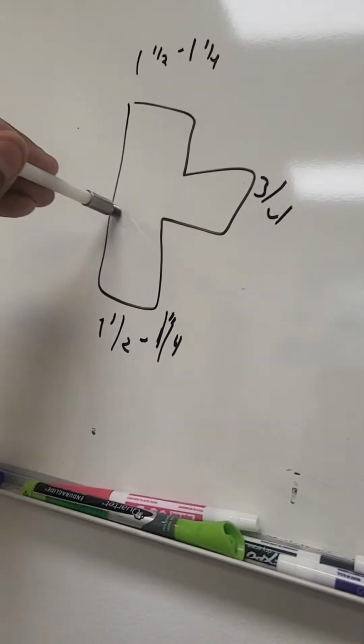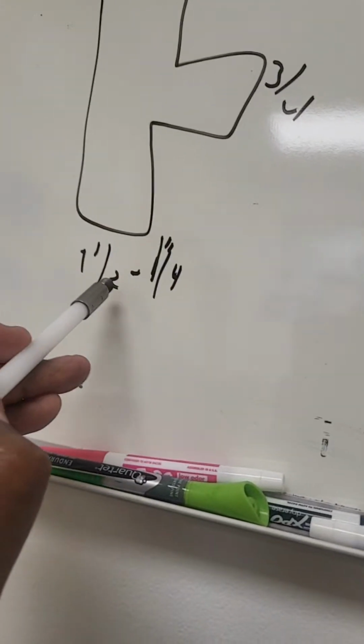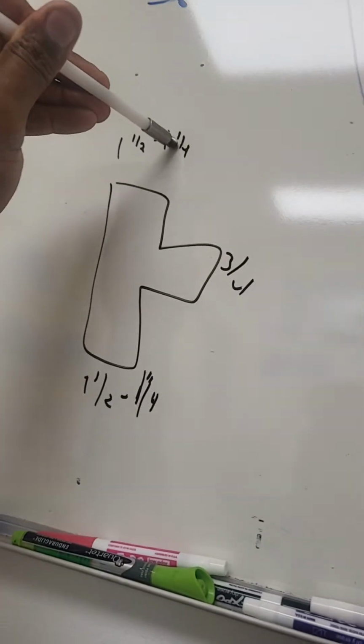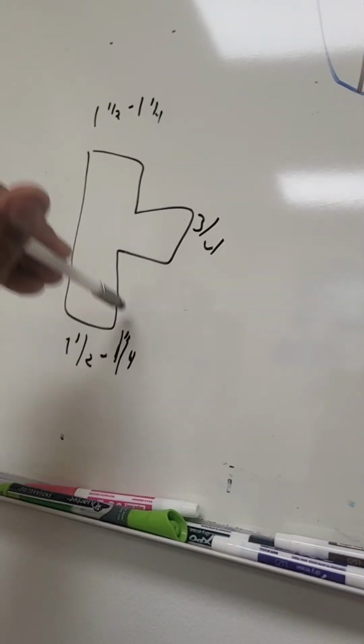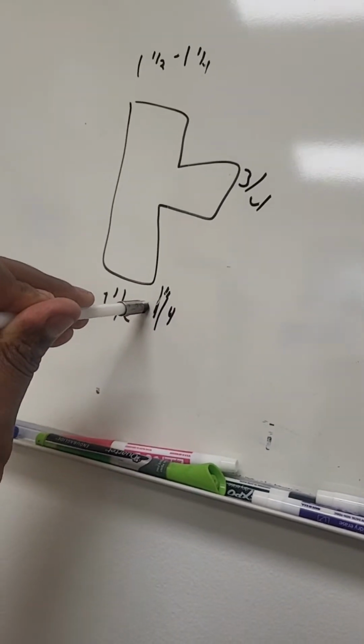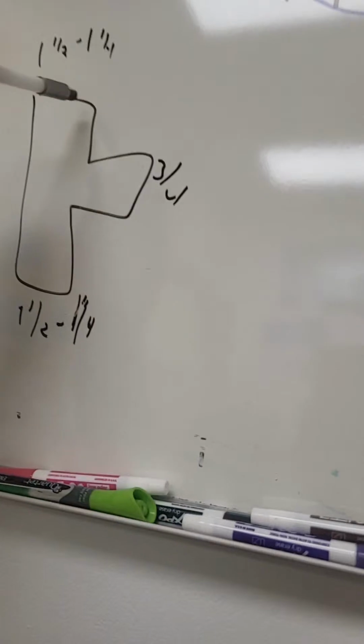Here's the tapping. For a low water cutoff, it's going to be 1.5 inches to 1.25 inches, meaning this is the supply, the piece coming from the supply to the boiler and going to the header. But the piece going to your low water cutoff is going to be 3/4 inch.